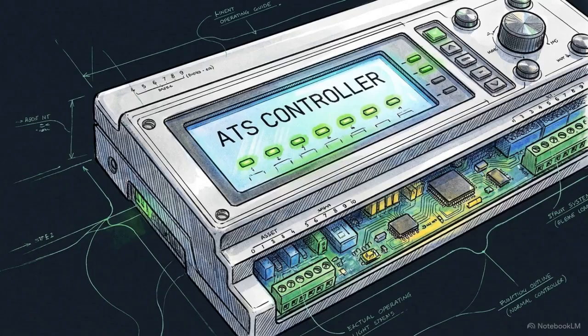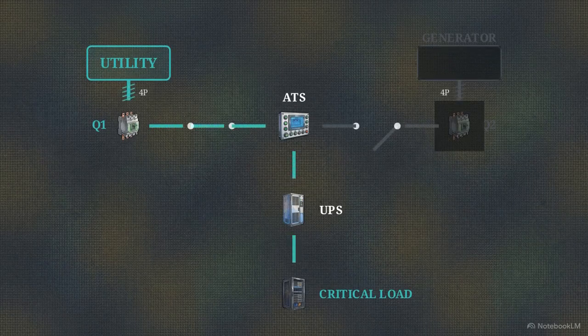The intelligence directing that transfer is the automatic transfer switch, or ATS. Sitting between the two incoming supplies, it acts as the single supervisory control point. It evaluates incoming voltage, confirms the alternate source is ready, and dictates exactly which power path feeds the facility.